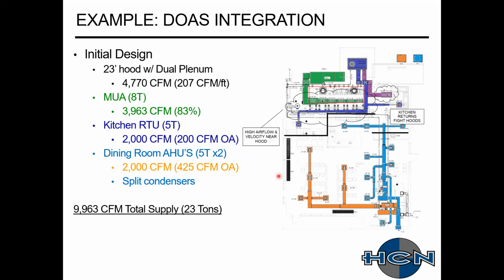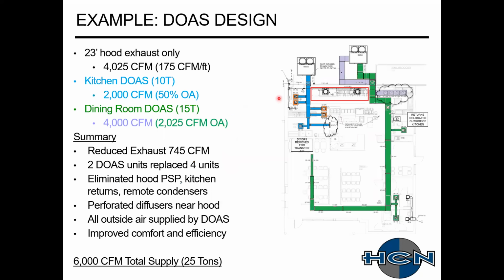So if we changed this design around and see what we can do. For this one, we went with 2 dedicated outdoor air units. The one in the kitchen, doing about 50% of the outside air load required, just 2,000 CFM, no return on that unit. Then the dining space, 4,000 with a little bit more than 50%, and returns moved away from the hood as far as we possibly could.